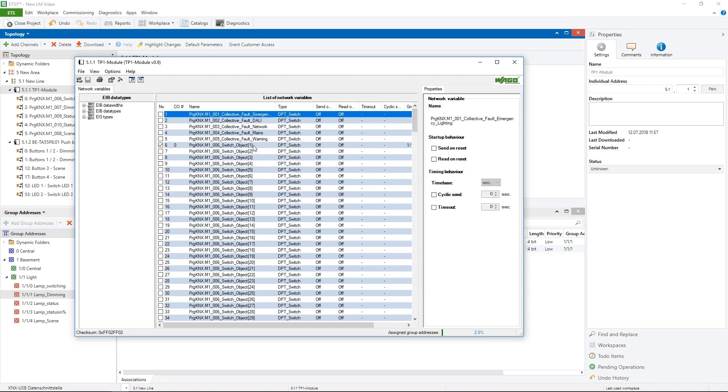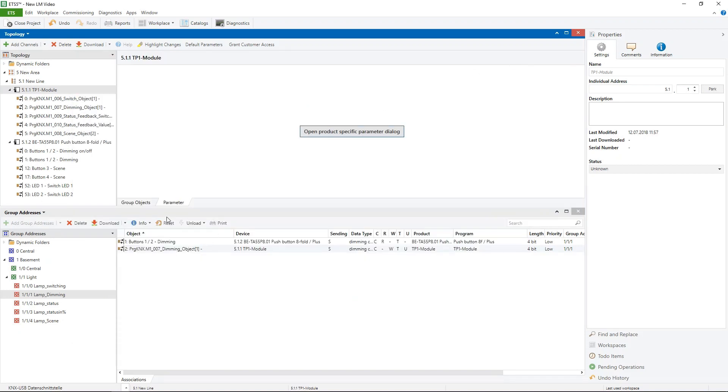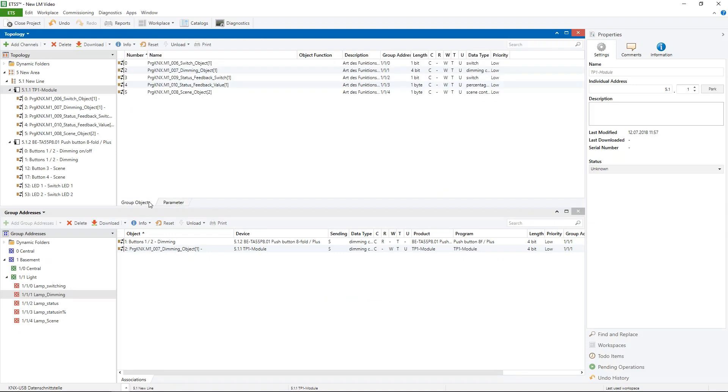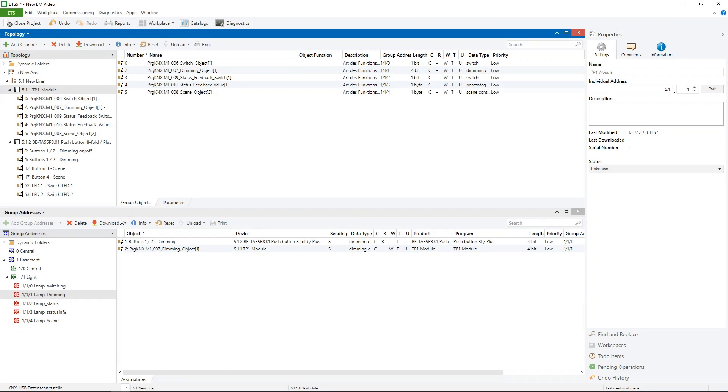And I will use the first KNX channel and the second one. Let's take a look which group object I have selected. So you see array index 1. I will use this to dim a lamp so I need the switch and dimming object, and for the second channel I need the scene object to call the scene.